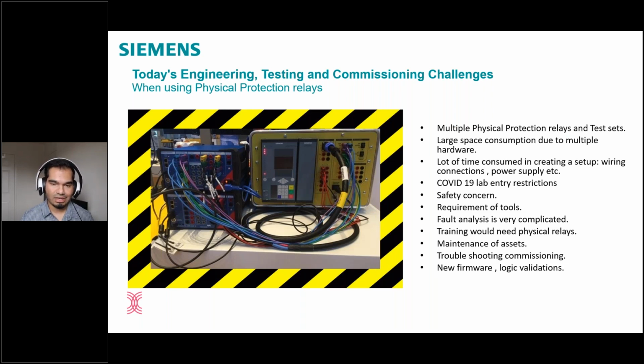So that's another challenge. New firmwares: you have a new firmware which has some enhancements, some bug fixes. You want to test it out and see whether it actually is usable or whether it actually solves your issue. So instead of actually loading it in an actual physical relay at site or in the lab, you test it on the twin. And also logic validations.